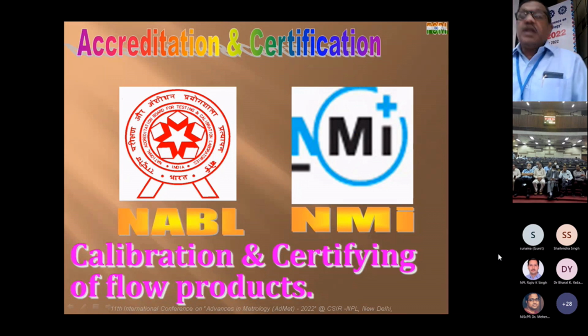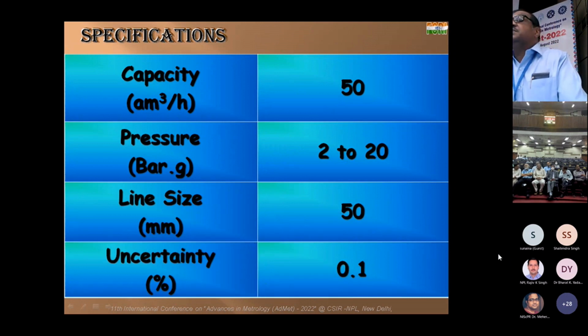As you know, our labs are accredited by NABL, and two facilities, the closed loop air test facility and the primary standard gravimetric facility, are both certified by NMI. We invited their experts and they certified that we are at par with their laboratory, and we follow ISO 17025. This is the specification of the particular lab: capacity 50 cubic meters per hour, pressure 2 to 20 bar, line size 50 mm (2 inch), and uncertainty is 0.1%.